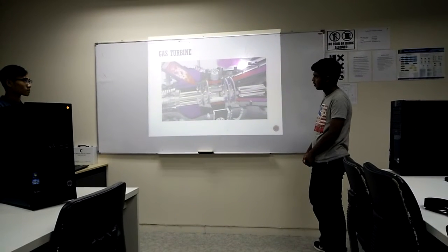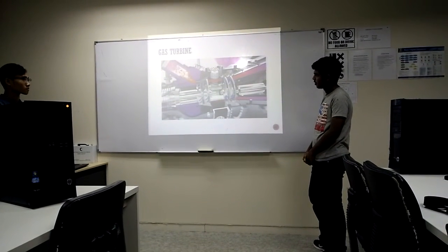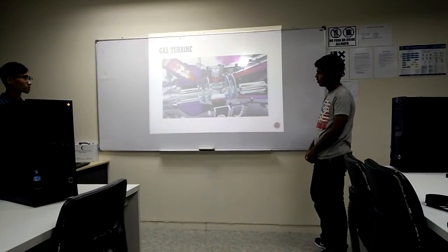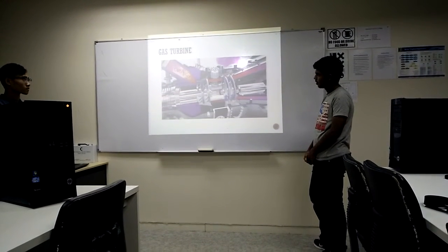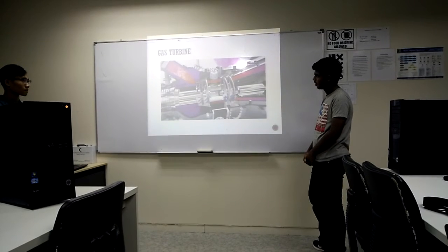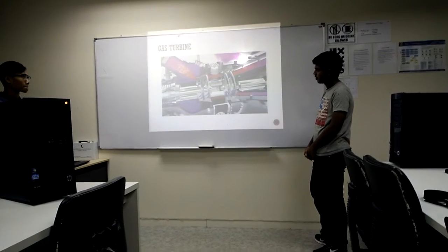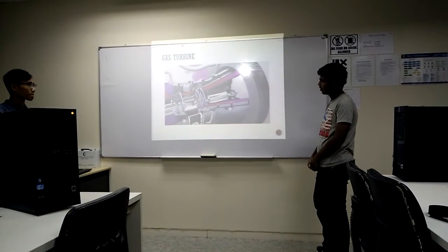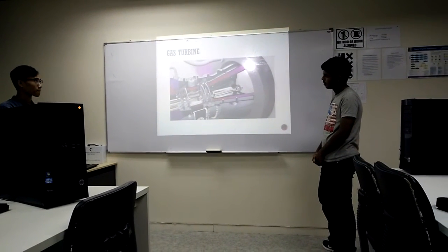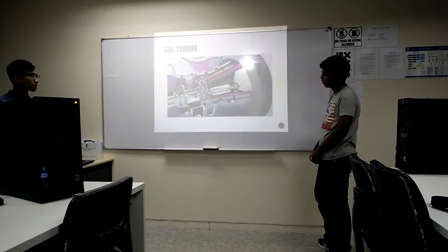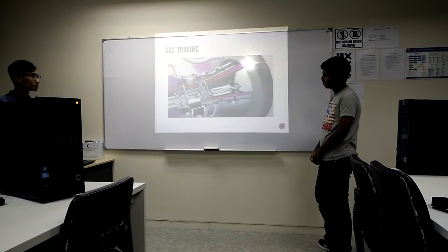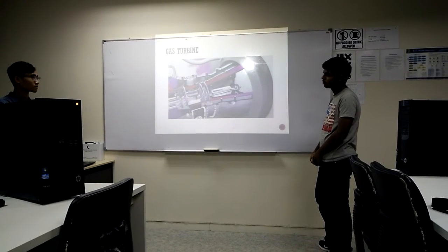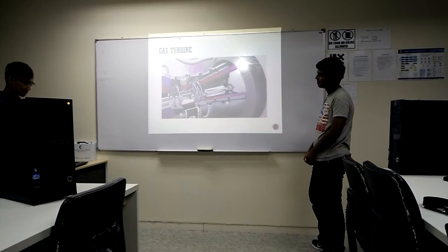The fuel gas air mixture expands due to the combustion heat to many times its volume. As a result, it flows at high speed first through the two rows of blades of the high pressure turbine and then through the low pressure or power turbine, thus driving both shafts. The exhaust gases flow through a diffuser into the outlet casing. Their high temperature of around 460 degrees Celsius can still be utilized, for instance, to generate steam.